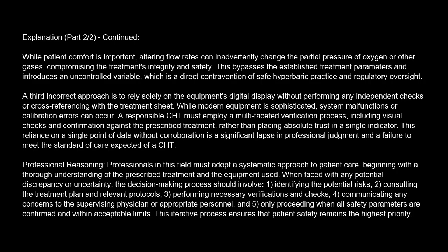and regulatory oversight. A third incorrect approach is to rely solely on the equipment's digital display without performing any independent checks or cross-referencing with the treatment sheet. While modern equipment is sophisticated, system malfunctions or calibration errors can occur. A responsible CHT must employ a multifaceted verification process, including visual checks and confirmation against the prescribed treatment, rather than placing absolute trust in a single indicator. This reliance on a single point of data without corroboration is a significant lapse in professional judgment and a failure to meet the standard of care expected of a CHT.